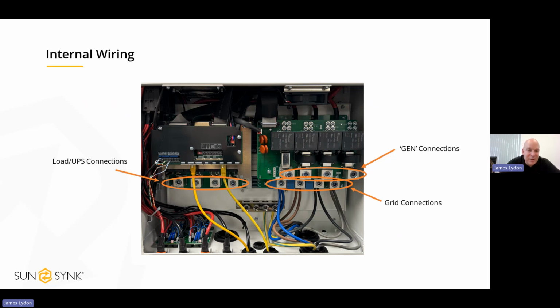And then on the left of the picture, you can see we've got the twisted pairs into the terminal strip, and that's for the CTs. If you're using an Eastron meter, that's obviously on an RJ45 end, and if you can see, you've got the two yellow cables. One of them is the BMS cable on this one, and the other one is the parallel cable. But if you're using the digital meter, it would go into the left-hand port labeled meter.